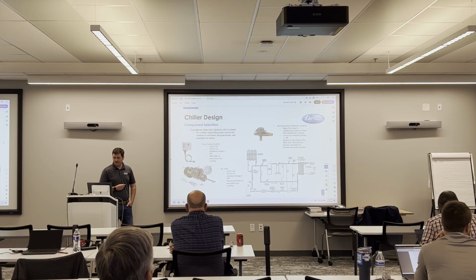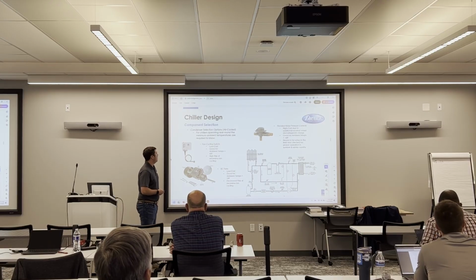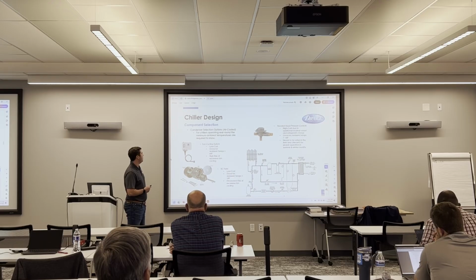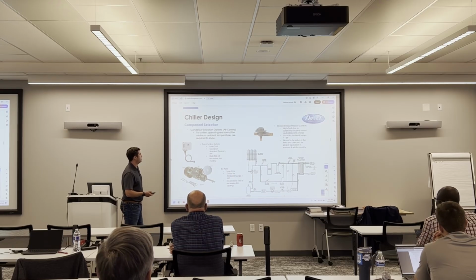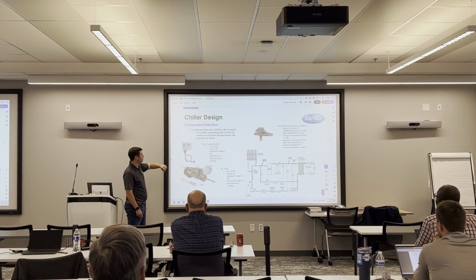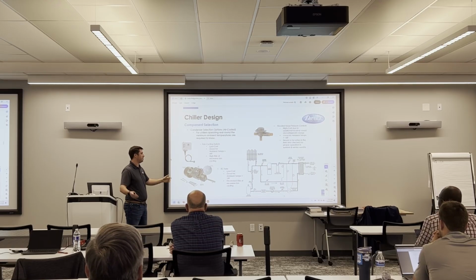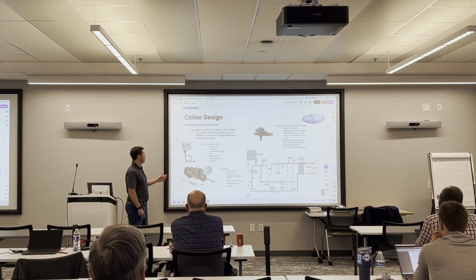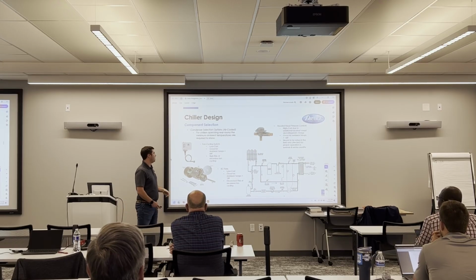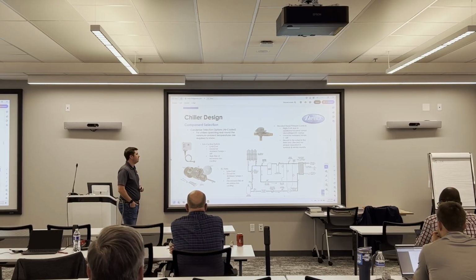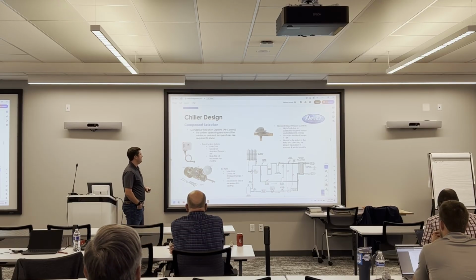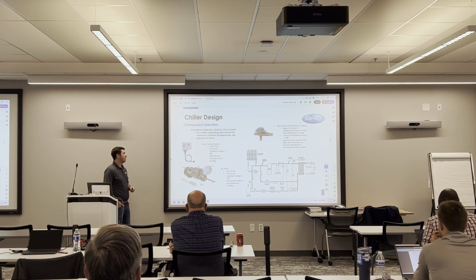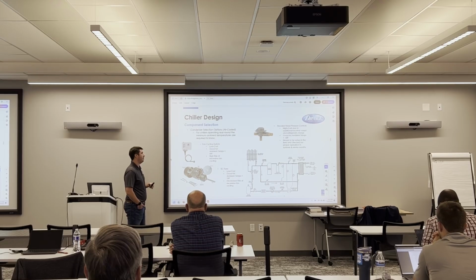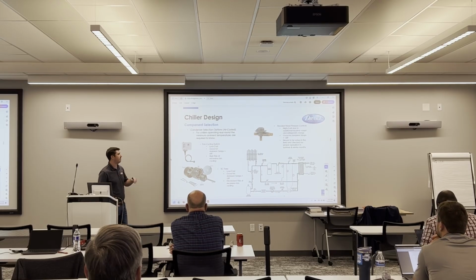So we'll start off with some of these head pressure controls for an air-cooled unit. The simplest form of maintaining head pressure is a fan cycling switch. It's just a switch you'd mount to the compressor discharge line, and it would essentially turn the fans on and off based off of the discharge pressure and keep your head pressure up. Low cost, you can pick them up anywhere. They're good for ambient temperatures down to about 60 degrees Fahrenheit. You do run a high risk of excessive fan cycling, so it's important you set these things up properly. You don't want to just set it up once, especially if you start the unit up in the summertime and set it up for summertime operation. Then I'm going back out there in the spring and winter to make sure our fans aren't kicking on and off like crazy, because you'll destroy your fan motors.